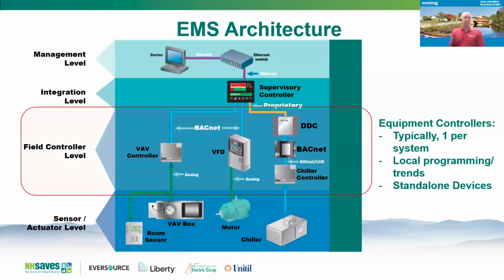Moving up a layer, you get to the equipment or field controller level. There's typically one controller per major piece of equipment. So, for example, on a VAV box, there's going to be a VAV controller mounted right to the box that usually also has an integrated damper modulation. And that is the controller, the brains of that piece of equipment. You can have another controller on a chiller or an air handler or a boiler.